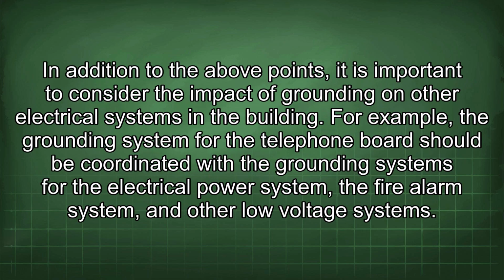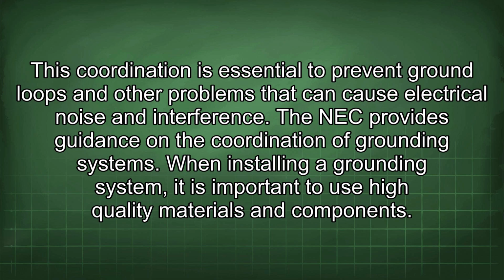In addition to the above points, it is important to consider the impact of grounding on other electrical systems in the building. For example, the grounding system for the telephone board should be coordinated with the grounding systems for the electrical power system, the fire alarm system, and the low voltage system. This coordination is essential to prevent ground loops and other problems that can cause electrical noise and interference. The NEC provides guidance on the coordination of grounding systems.